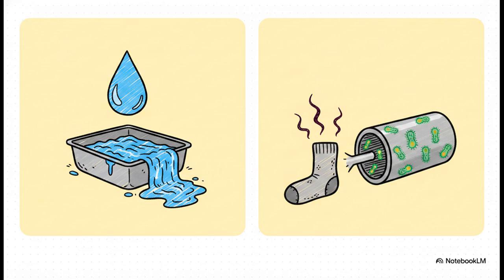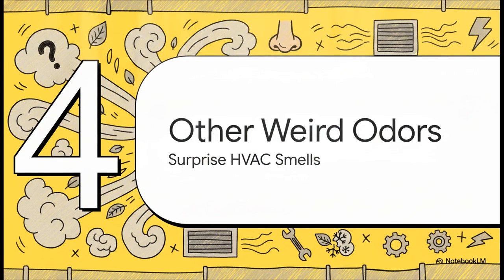On one hand, a musty or mildew smell usually means you have moisture or mold sitting in a backed-up condensate drain pan, or you just have a really dirty coil. On the other hand, that dirty sock smell points straight to coil biofilm. To put it simply, musty often means standing water, while dirty socks means you've got a bacterial layer living right on the coil itself. And spoiler alert, air fresheners won't fix either of these because the source is buried deep inside your air handler. Section 4.